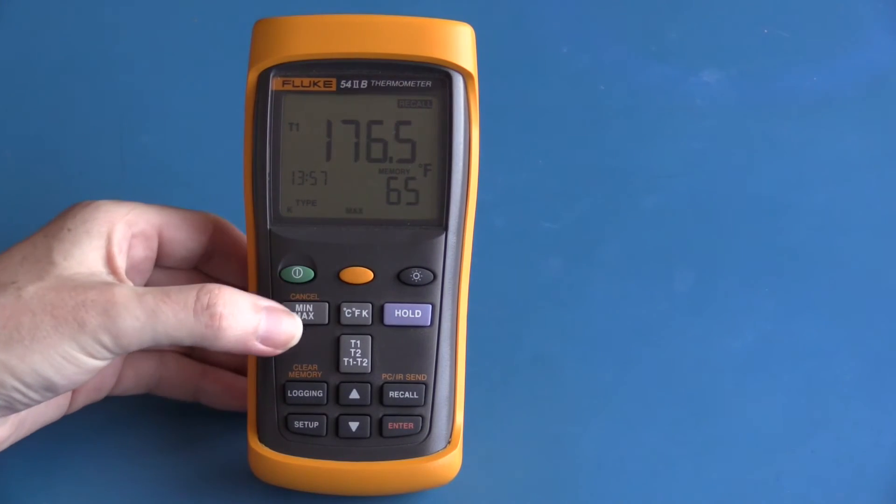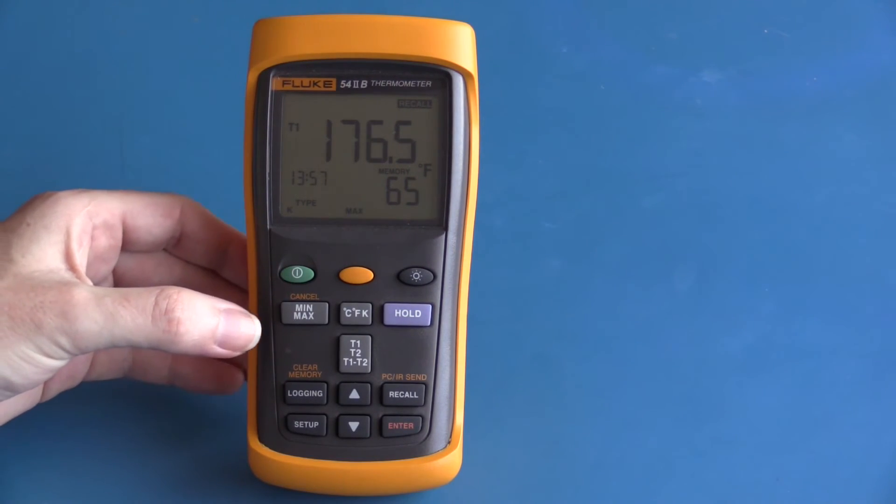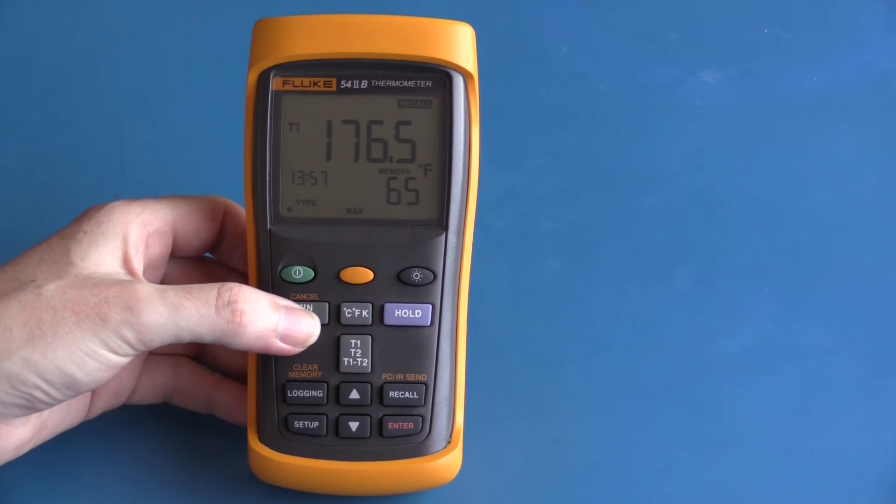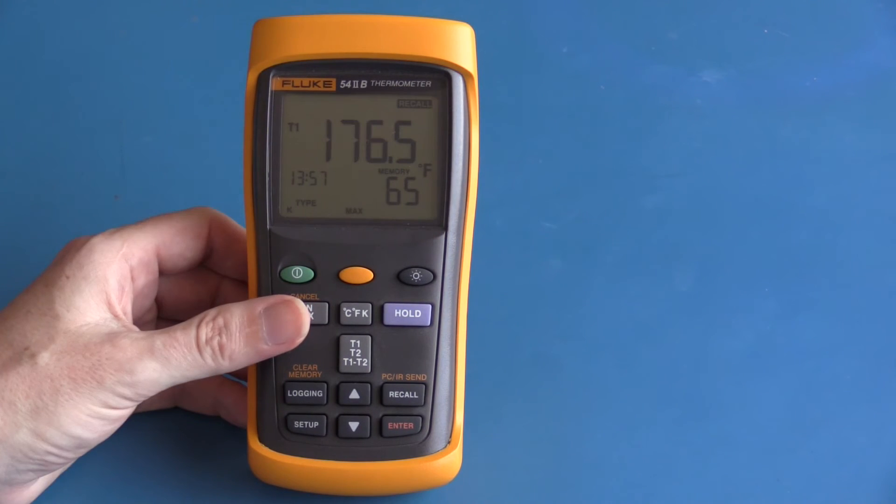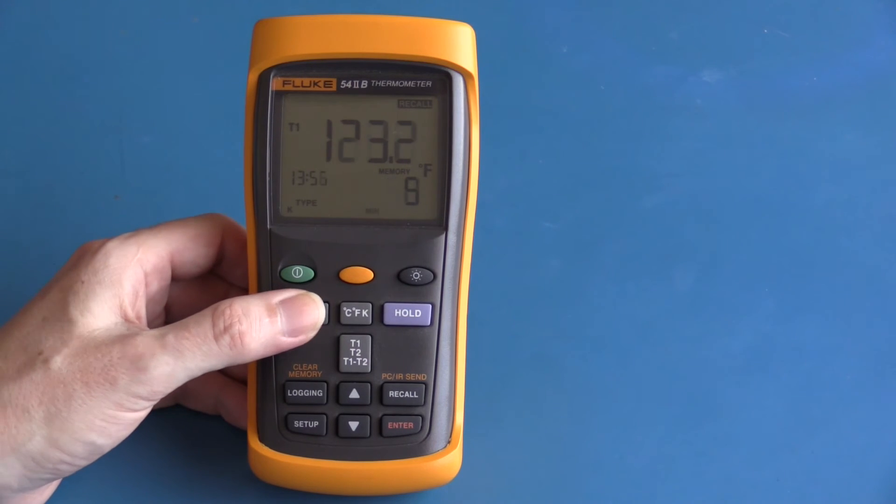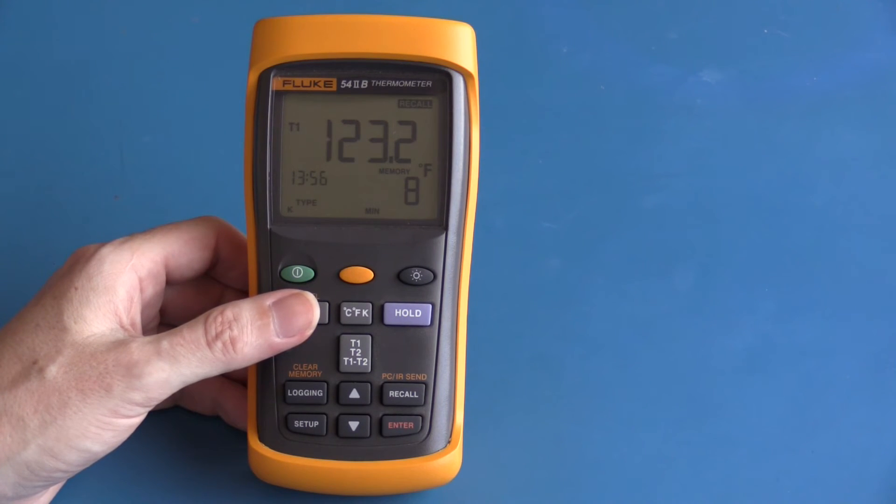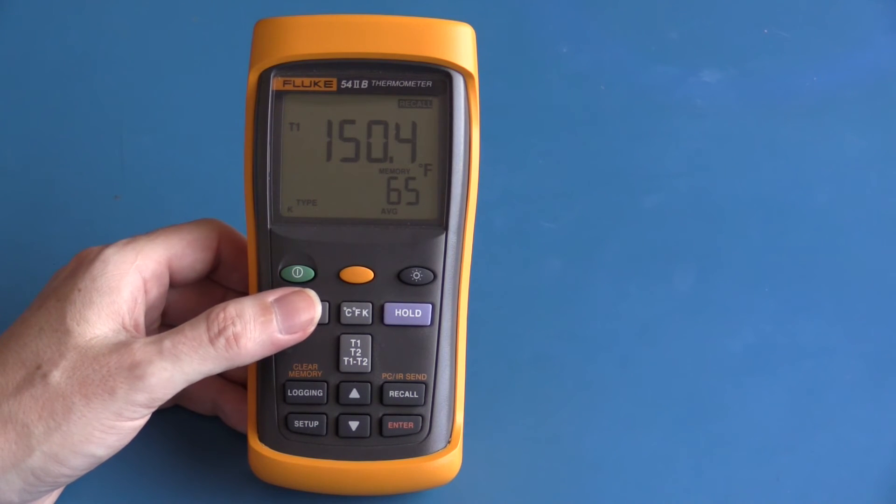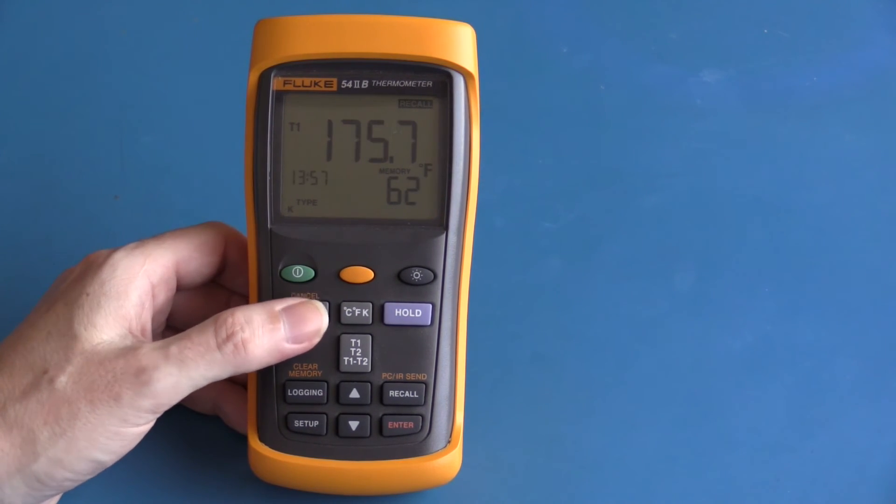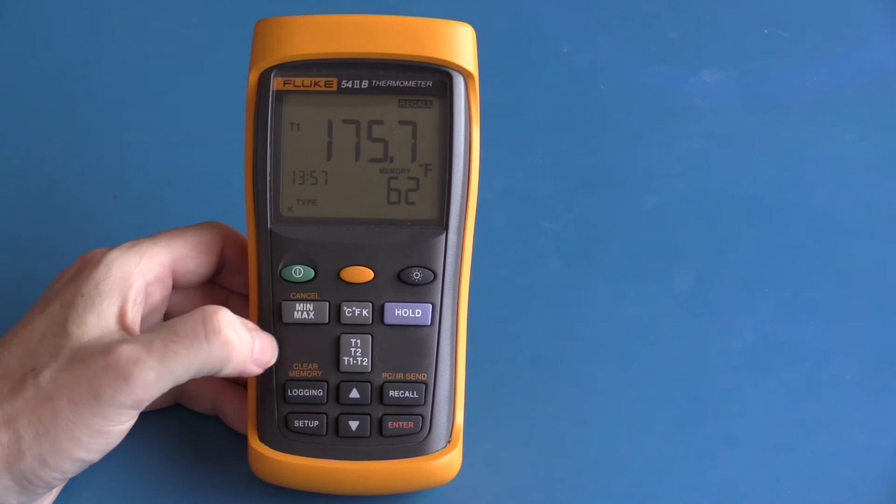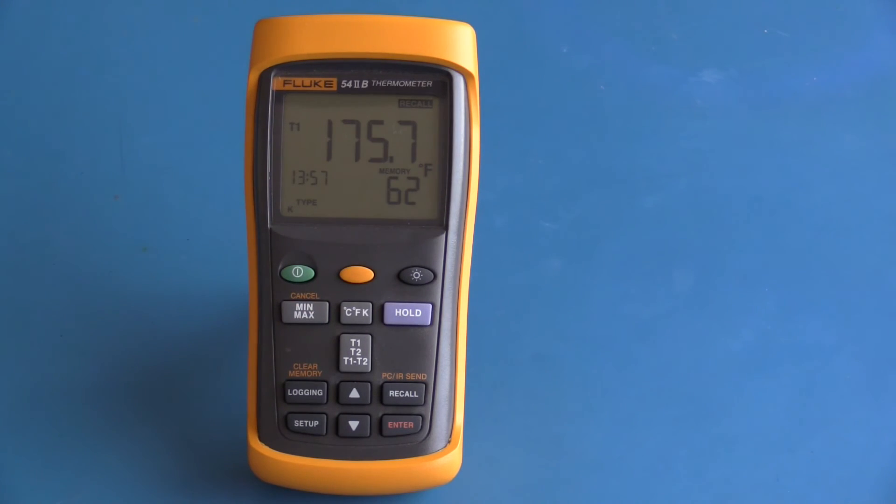Also the min and max functions work on log data. The maximum reading was taken at 13:57 and it was 176.5 degrees Fahrenheit. The minimum was 123.2 degrees Fahrenheit and that was logged at 13:56, and the average is 150.4 degrees Fahrenheit. The temperature units can also be changed while viewing the log data. We're currently set to Fahrenheit, this would be Kelvin, and this would be degrees Celsius.